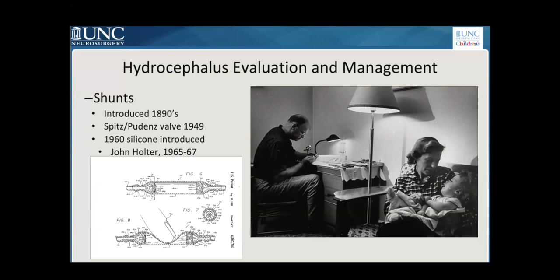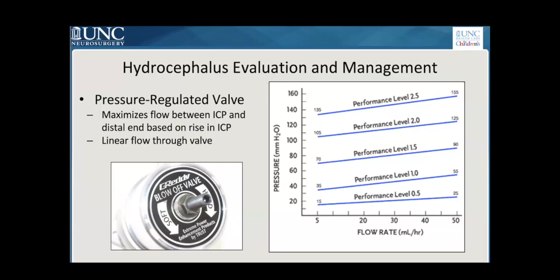So the different types of shunts we have, there's fixed pressure, and then we have these programmable or adjustable shunts. So pressure regulated valves are actually pretty simple. This is just one example of pressure curves on the right. You can pick a 1.0 or a 2.0 and know how much flow is going to go through the shunt valve. These really work like a radiator blow-off valve. So as pressure in the brain goes up, the shunt valve opens more and more fluid flows through. As the pressure comes down, less fluid flows through. So they really do help regulate the amount of flow of spinal fluid out of the brain.